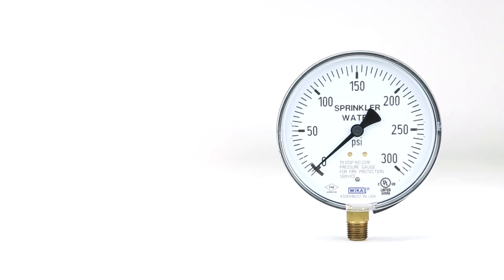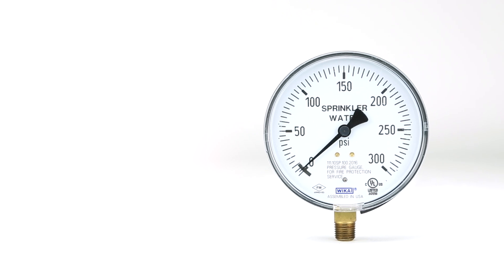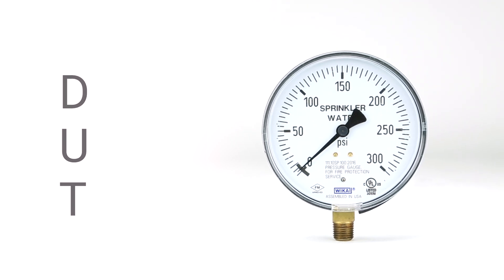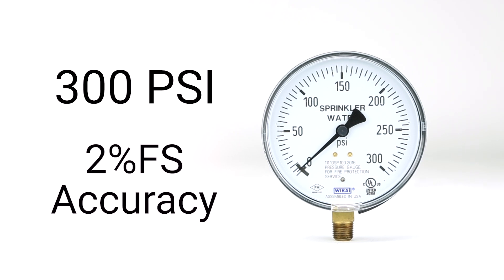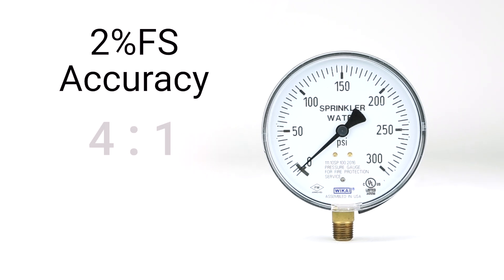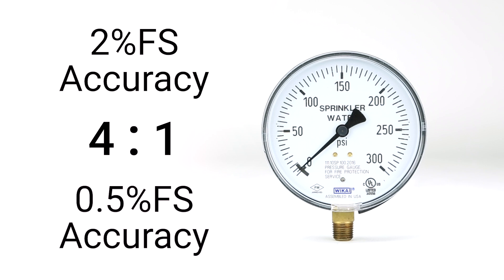To begin calibration, we select our dial gauge, also called the device under test, or DUT. It measures up to 300 psi, with a maximum accuracy of 2% of its full span. In order to do a 4 to 1 calibration, we will need a reference that is at least 4 times more accurate. In this case, that's 0.5% accuracy or better.